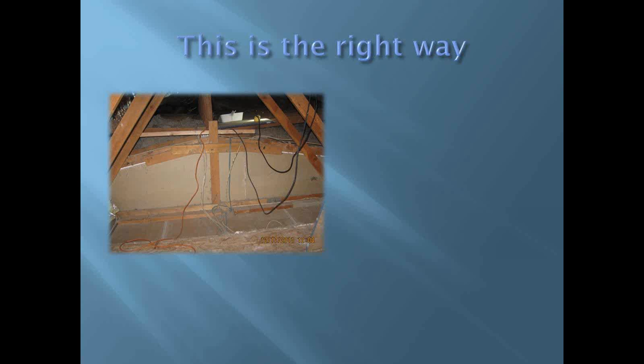And the problem is that we're not putting backing on the back of it. And I've gotten in trouble with the building officials by telling the HVAC guys, don't give them full rating for these walls. When you're doing the heat load calcs, anything that isn't backed, cut that in half. Then you'll have the system sized to meet the actual load. It doesn't sound right. It doesn't sound like what we should be doing in code, but that's what will actually make those rooms function. So it's just something I can't really overstate: we shouldn't have insulation just hanging out in places of the house.